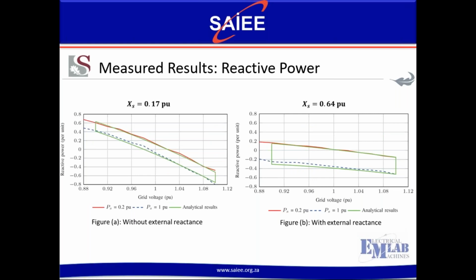The slide shows the reactive power versus grid voltage and supply power for the two test case scenarios where the inductances were added and where they weren't added. Once again, it can be seen that a good agreement exists between the measured and the analytical results. What's interesting to note is that for figure B, where the external inductances were added to the generator terminals at low power conditions, the slip synchronous permanent magnet generator acts as a passive reactive power compensating device, where it supplies reactive power when the grid voltage drops and it absorbs reactive power when the grid voltage increases. This is typically how grid voltage compensation is done.